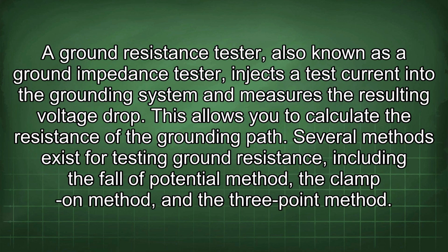A ground resistance tester, also known as a ground impedance tester, injects a test current into the grounding system and measures the resulting voltage drop. This allows you to calculate the resistance of the grounding path. Several methods exist for testing ground resistance, including the fall of potential method, the clamp-on method, and the 3-point method.